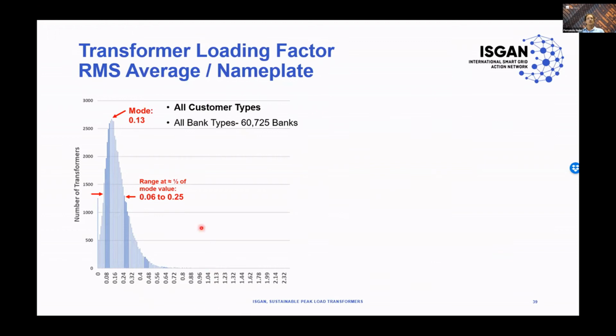What he found is that the mode, the most repeated value, is 0.13. This means that average loads of distribution transformers are as low as 13%. And the bulk of the situations is between 6% load and 25% load. So this confirms that by and large, distribution transformers are very poorly loaded. Of course, they have to be sized for peak situations, but this happens very rarely in time. Some transformers, very few, reach average loads of 50%, which is the optimum, as Alan said before.